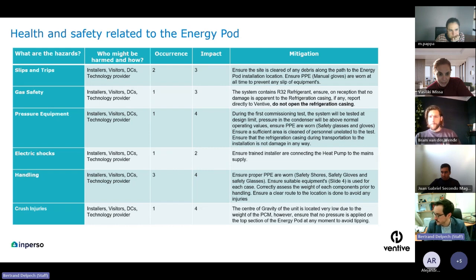And finally, crush injuries. It's very unlikely to happen, but again, this is all related to the proper selection of the tools to take the heat pump from one place to the other. Normally, if the assessment is done properly, there is no issue at all of that happening. However, we registered it as a risk because it is a possibility, though very, very unlikely. What we implemented to prevent that is a very low center of gravity, so we prevent any tipping during transportation, which is very important because all the PCM is located at the bottom.